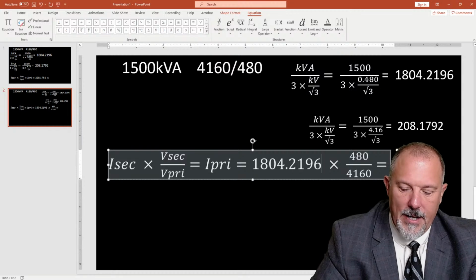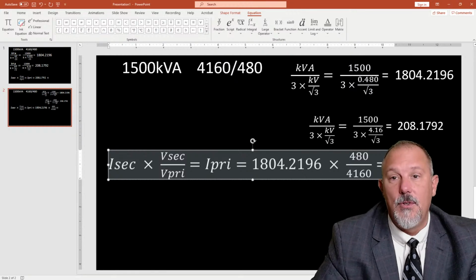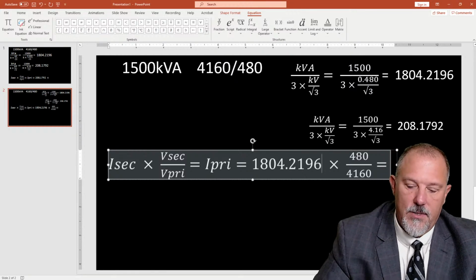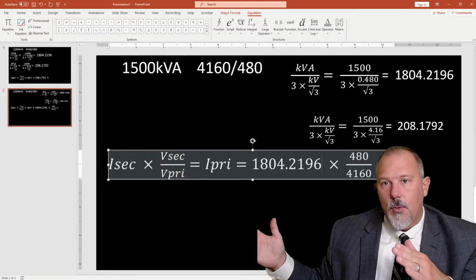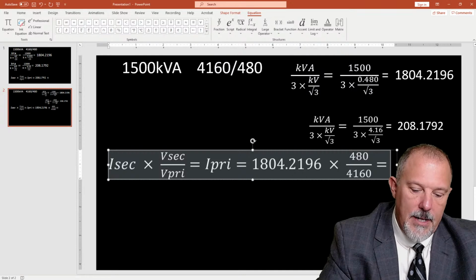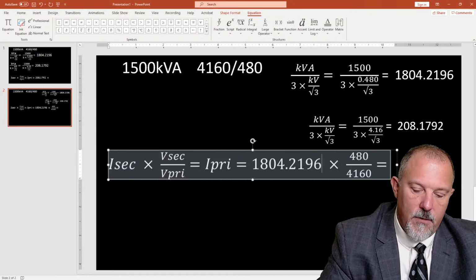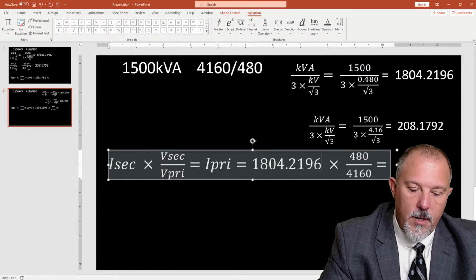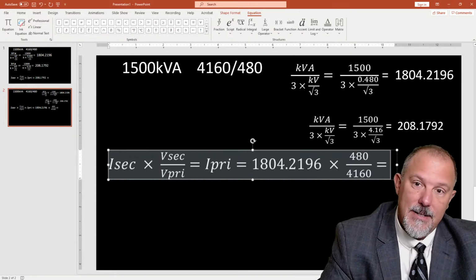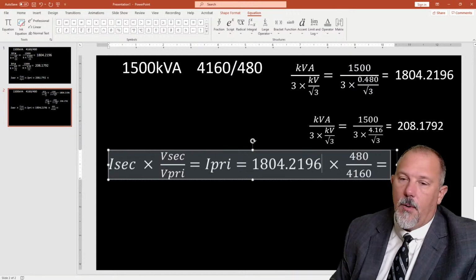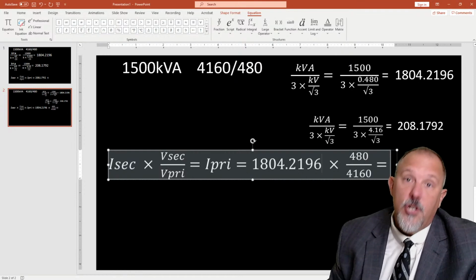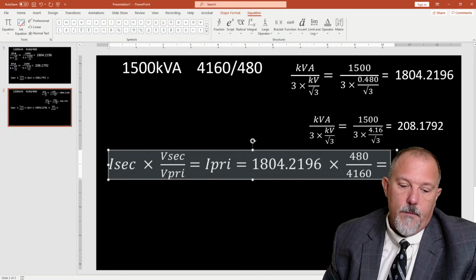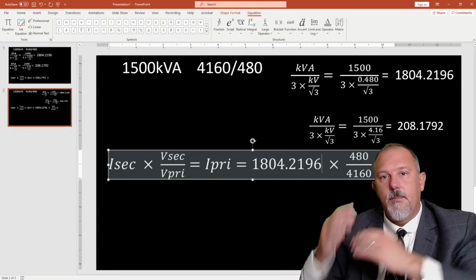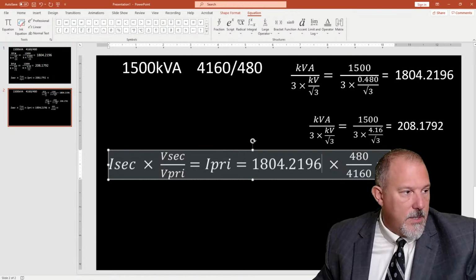1804.2196 times 480 divided by 4160 is 208.1792. So if you carry all the decimal points out, now if I just did 1804 times 480 divided by 4160, I get 208.1538, which is a little different than 208.1792. I would still say 208 amps. So you can just simply do that math, and that's what he was talking about.